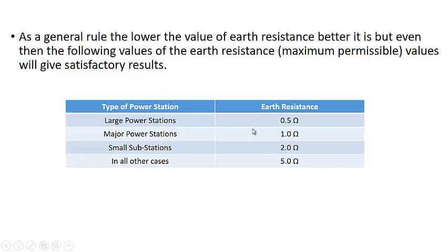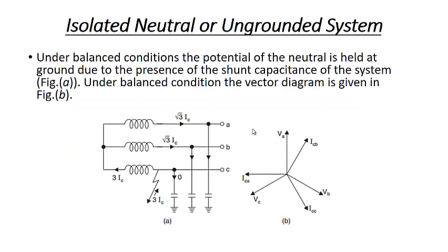This is all about earth potential, equipment earthing, touch potential, and safe currents flowing through the human body, and based on that we design the resistance of the grounding structure in case of substations. So it is a part of a design perspective. We did it on the design perspective. So now come to the neutral system, or you can say grounded system. But before going to the grounding of the power system, we'll first see what are the disadvantages and problems that are associated with the isolated neutral or ungrounded system.